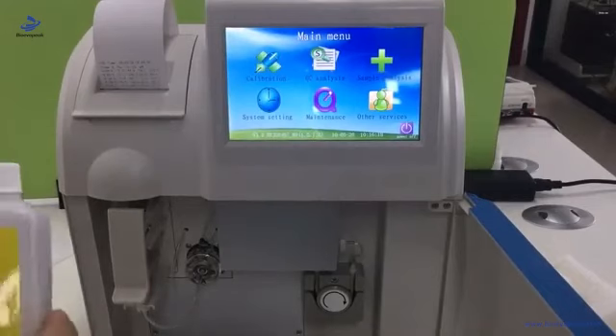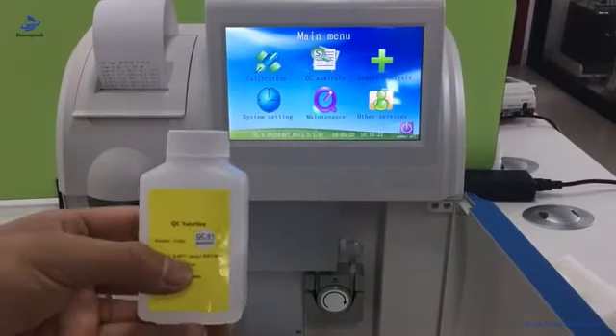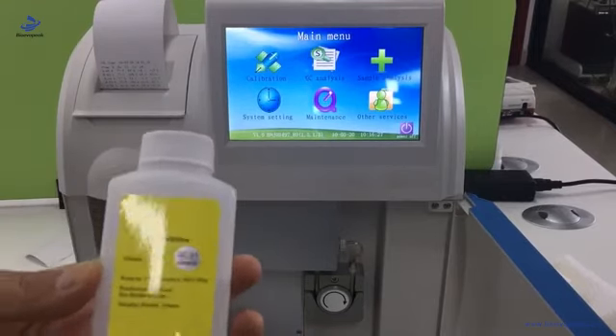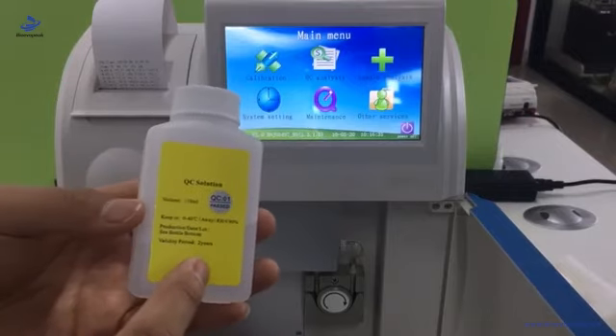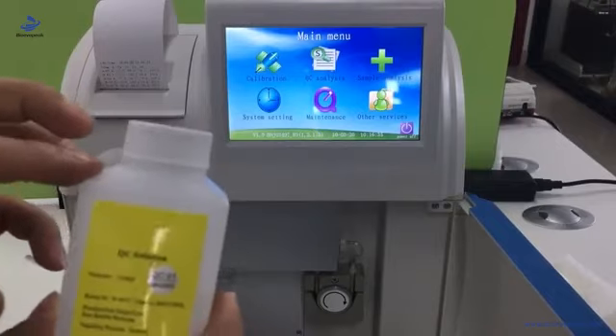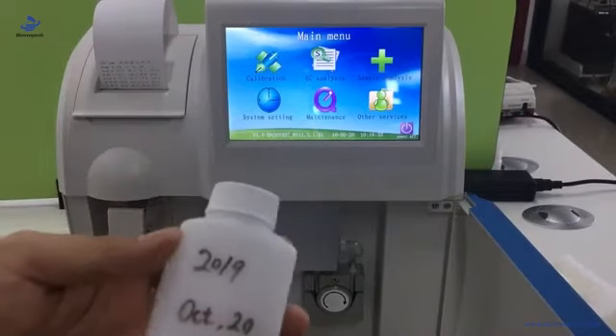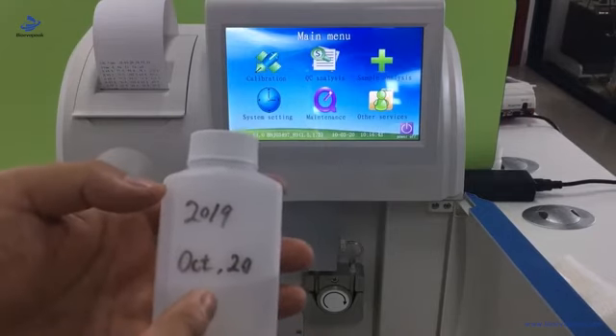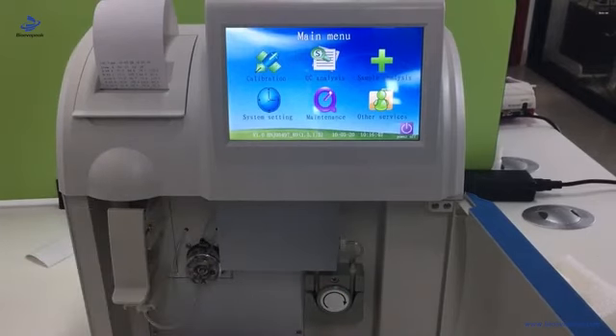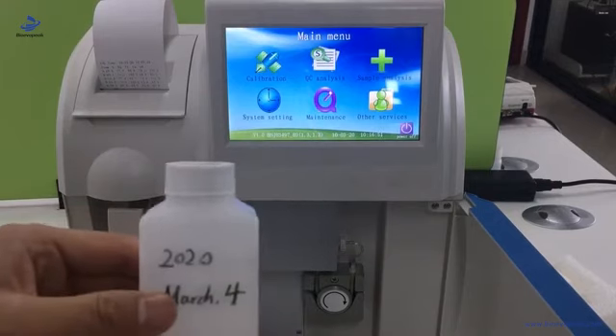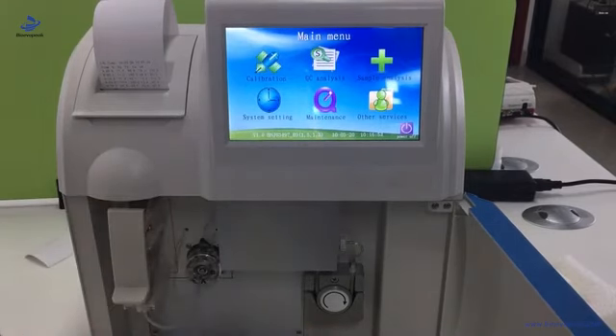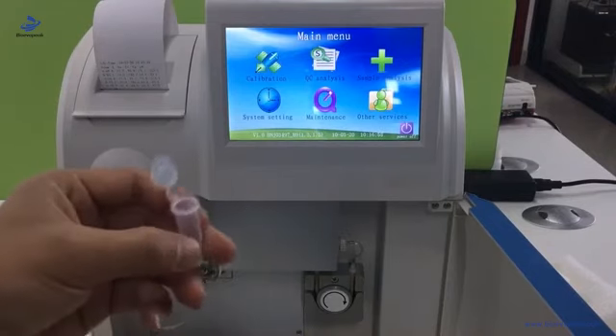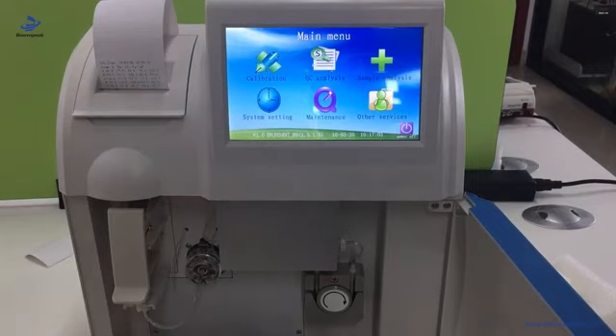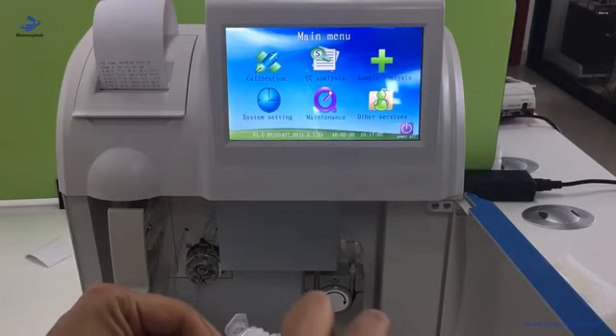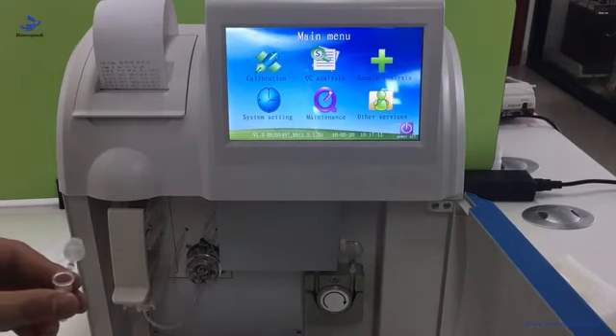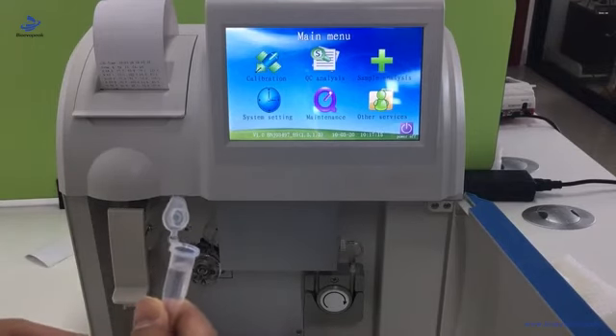Generally, we use the QC solution as a sample to do the sample analysis for demo. As you can see, the warranty period of the QC solution is 2 years, but when it's opened, the warranty period is only 1 month. So we need to use a marker pen to note down the open date on the bottle, so it's obvious for the end user. That one is already invalid, so we use another one. This one is valid. So let's take another bullet tube to take some sample first. Okay, let's think of this as the human sample to do the sample analysis.